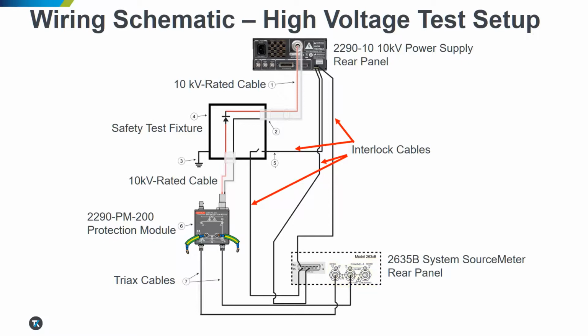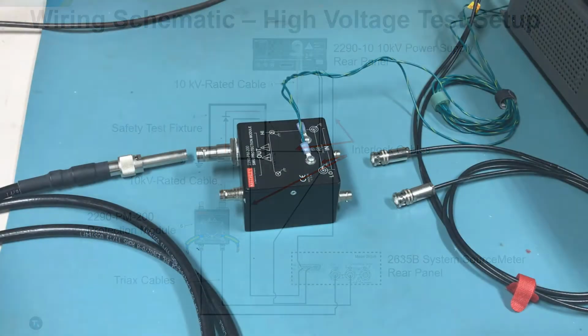For safety, neither the high voltage supply nor the source meter will operate unless the cover of the test fixture is secured to the case. A proximity switch on the test fixture case and on the cover must be closed to allow high voltage output. Interlock cables, shown on the right of the schematic, connect to both the interlock detection input on the high voltage supply and the interlock detection input on the digital I/O connector of the source meter.